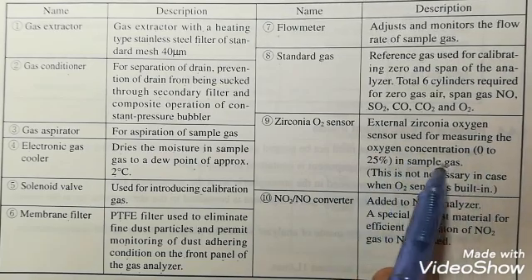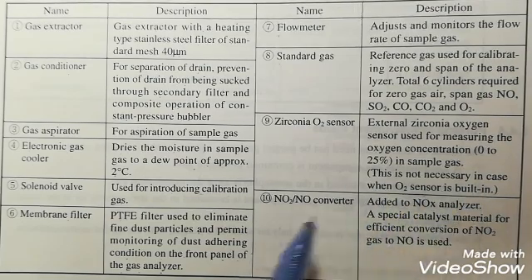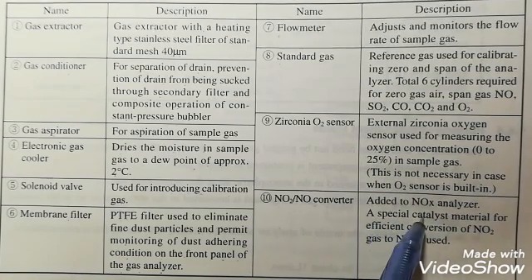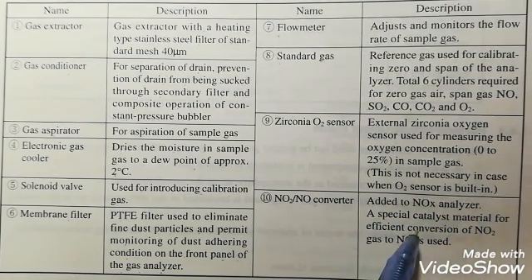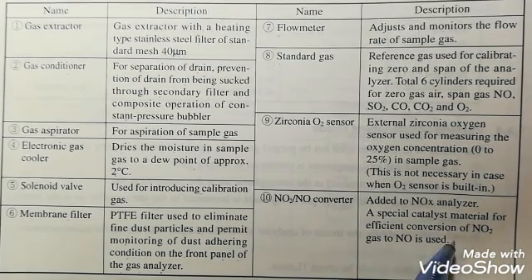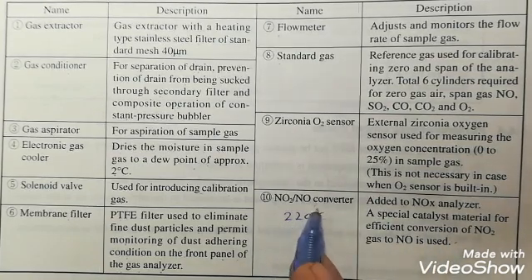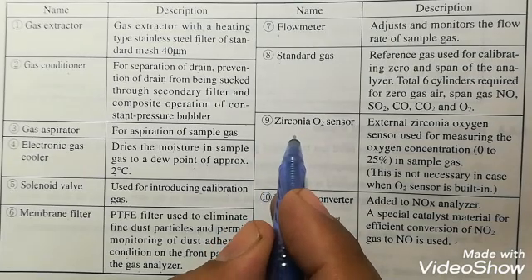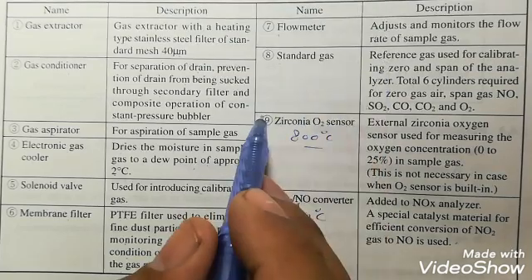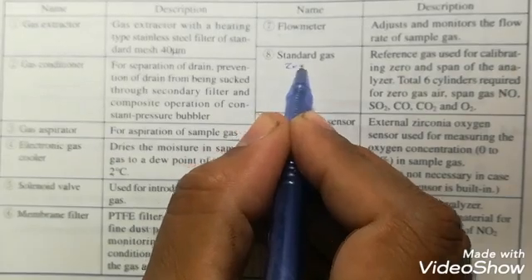So we will give the standard gas for zero and span. Zirconia O2 sensor is an external zirconia oxygen analyzer used for measuring the oxygen concentration in sample gas. NO2 to NO converter is used to convert NO2 into NO using a special catalyst material for efficient conversion. This NOx NO2 to NO converter uses 220 degrees centigrade, and the zirconia uses 800 degrees centigrade.